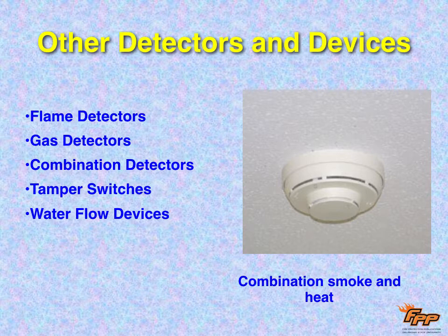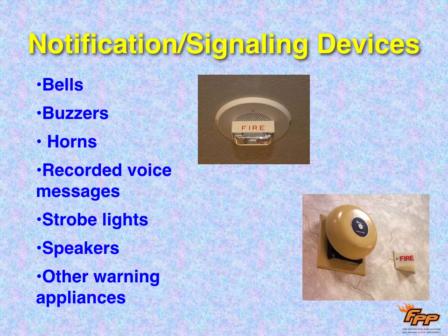There's another kind of device with sprinkler systems that senses when water is flowing through the sprinkler system and will set off the alarm. Every automatic sprinkler system is required to have an automatic alarm system in conjunction with it with a water flow device. Now, lastly, we have the notification devices, and these are going to be the devices that let people in the building know that something's wrong. So we have bells, buzzers, horns, recorded messages, strobe lights, speakers so that someone can speak from those control rooms that we talked about earlier. Mostly, we're going to see horns and strobes. That's what's most common. And here's a horn strobe on the top picture. Here's a bell with a strobe next to it on the bottom right picture.